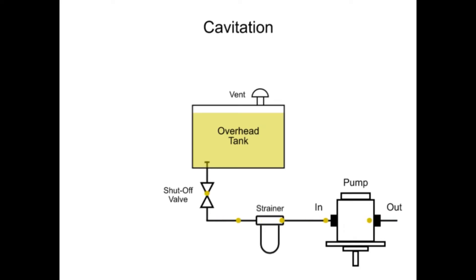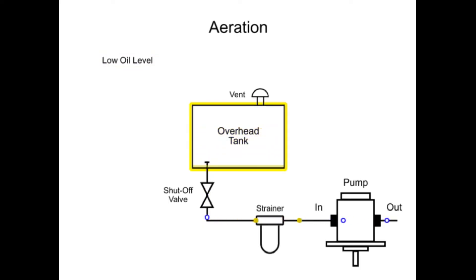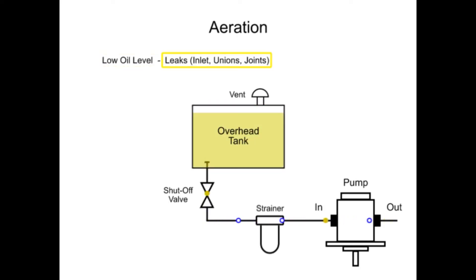Another form of cavitation is called aeration and is caused by air entering the oil stream. This can occur for a variety of reasons, including a low oil level in the reservoir or leaks in the inlet plumbing line.